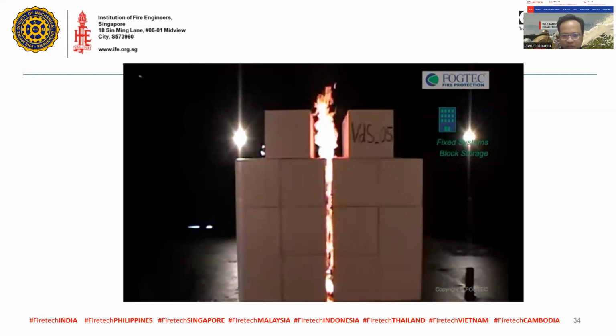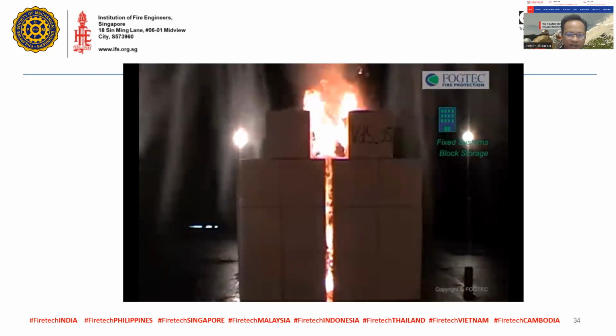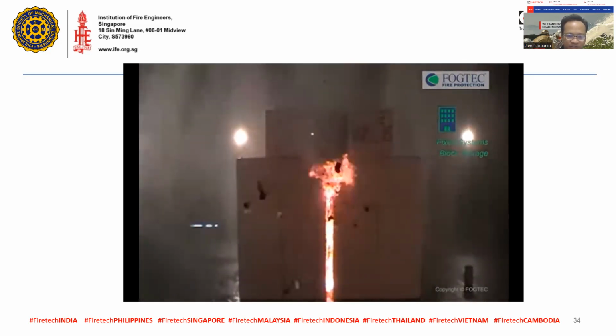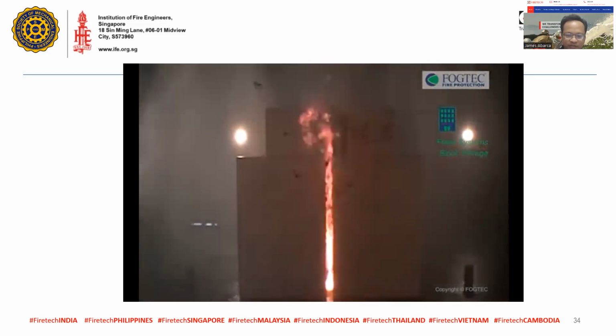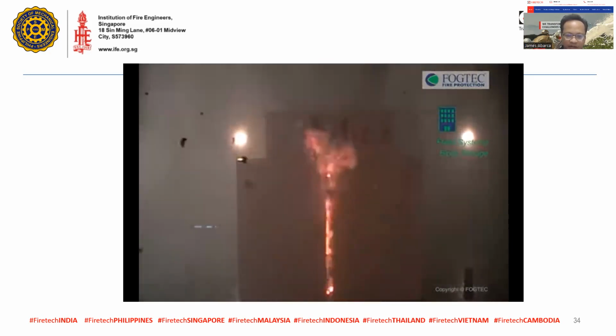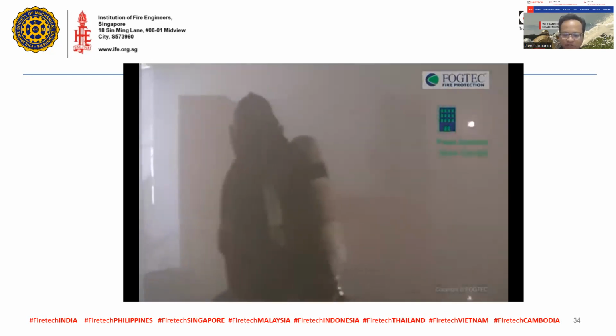Notice again how quick the response of the water mist system is and how effective it is in suppressing. See that? Some parts of the burned items are being blown by the high pressure water being applied. Then of course, as we have mentioned, it will envelop the fire. It will inert oxygen. It will cool. It will absorb the smoke. Then there you go, you have the suppression.